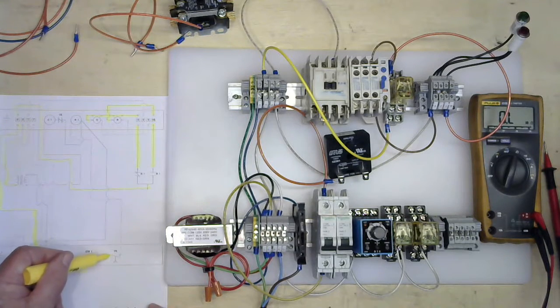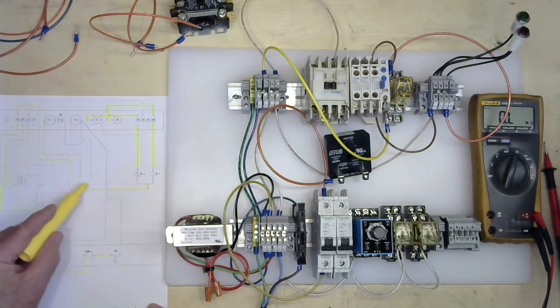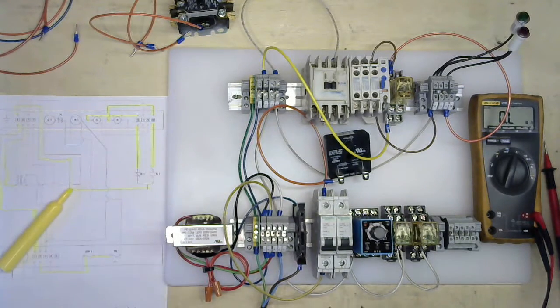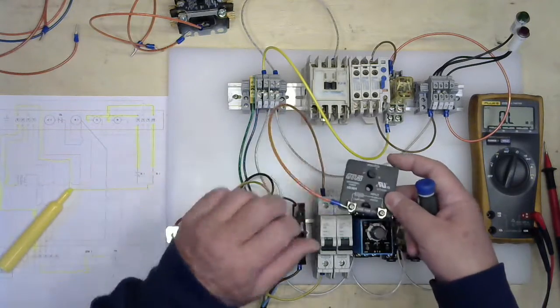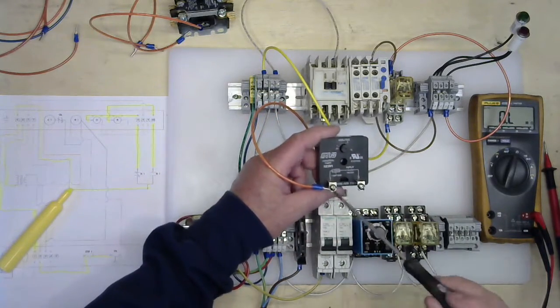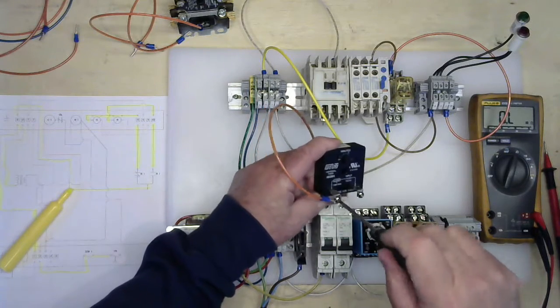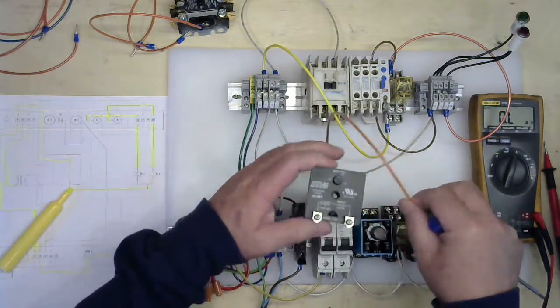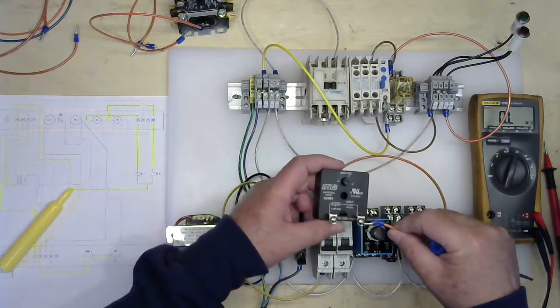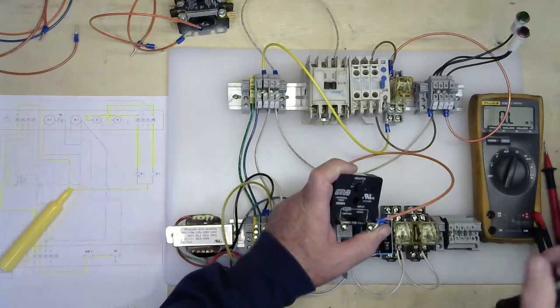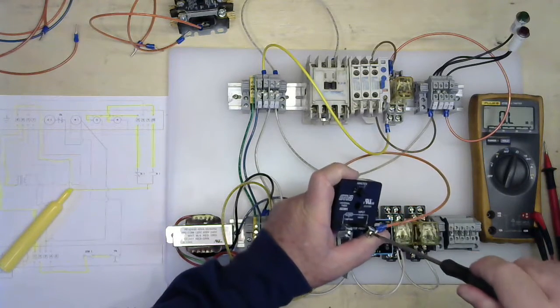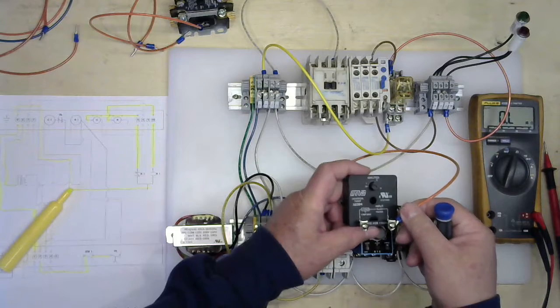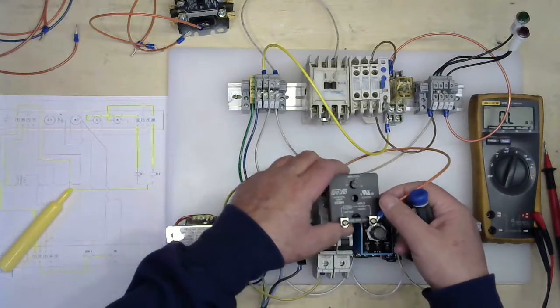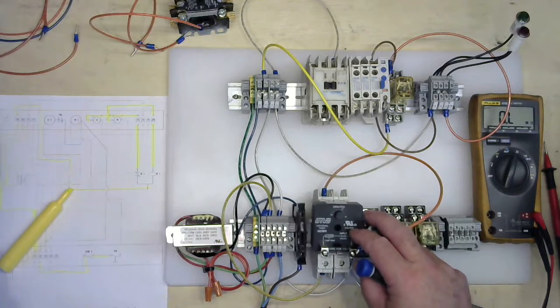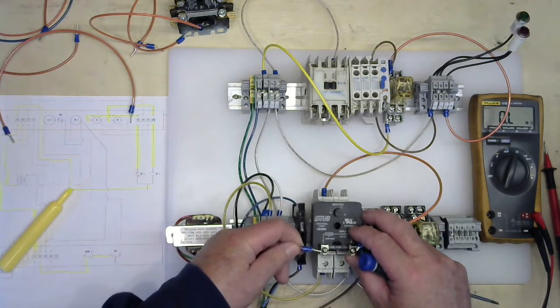So we already have this wire. Now we have to leave the time delay to our relay. One of the problems we have here, I just connected this to our load. We want it to be on our input. So I'm going to take this one back off and connect it back to my input. We have to make sure that when we have 24 volts coming in, the time delay will start timing out. So now I have a wire here connected. I'm going to grab a different color wire and connect it to my output.